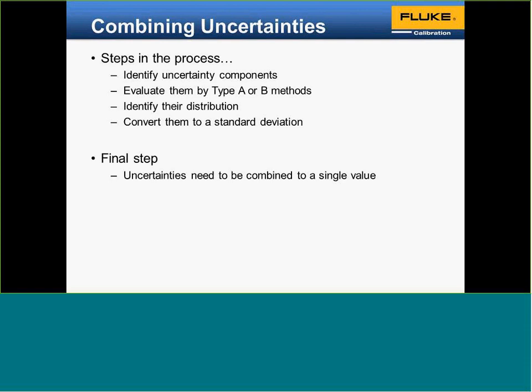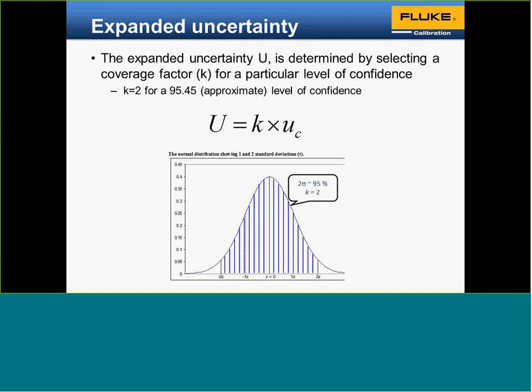We've talked about uncertainty components, type A and type B methods, and standard deviation, and now we combine all contributors into a single value. So I have the uncertainty contributors at 1 sigma, times K, which is the coverage factor, which applies for infinite degrees of freedom. In my budget I use the Satterthwaite formula with the student t table to combine all my contributors and their degrees of freedom, to ensure I can use the number 2 multiplier.